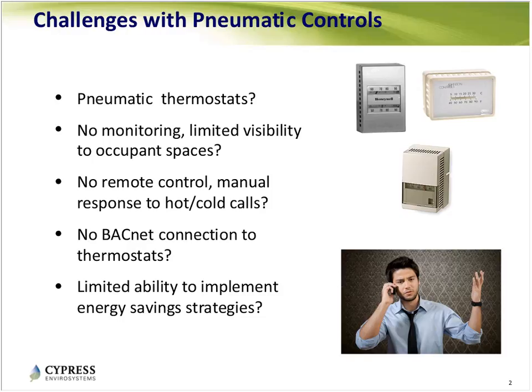Third issue is there's no BACnet connection. Many of you who run buildings or have invested in buildings have modern automation systems from Johnson, Honeywell, or Siemens controlling your building. But these thermostats, because they're not networked, not communicating, not programmable, cannot talk to your building automation system. Usually you communicate through BACnet or LON, different protocols for your building automation system, but pneumatic thermostats don't support that. I see a question coming in about whether the retrofit solution will talk with BMS, and yes, it definitely does. I'll show you shortly how you'd retrofit these older stats and build an integrated DDC system with your building automation system.